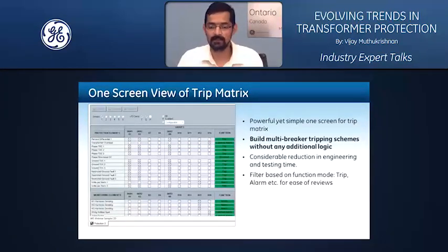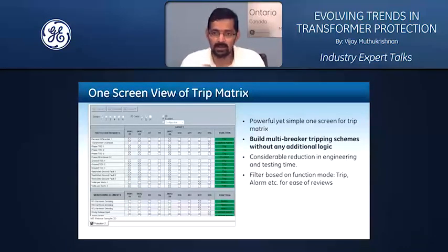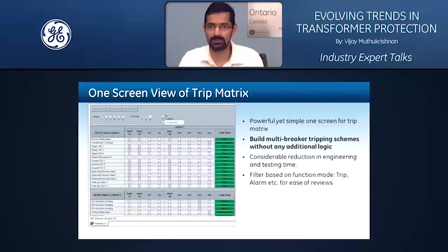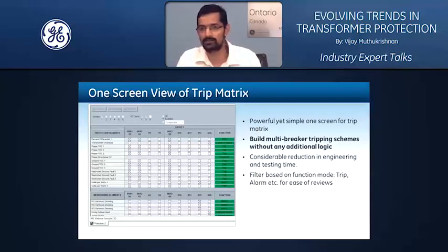All these things can be simplified from a single screen. You don't have to do FlexLogic or any other logic editing to build these types of common complex schemes of trip matrices. You can do it from a single screen of Protection Summary, and also within the Protection Summary, you can view which elements I have configured for just tripping, which elements I'm using for alarm, and which elements I'm using for monitoring. In a single snapshot, you can view and make engineering decisions: okay, this is what I am doing, this is how it is configured, it makes sense to me, I'm happy with it, move on. Your whole process of building setpoint files and validating setpoint files can be made very, very simple and fast.